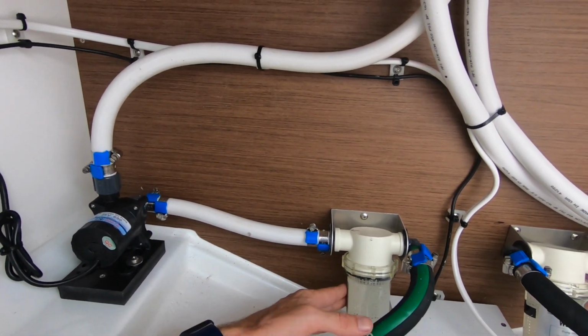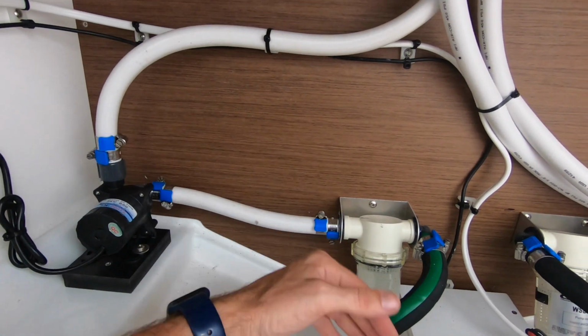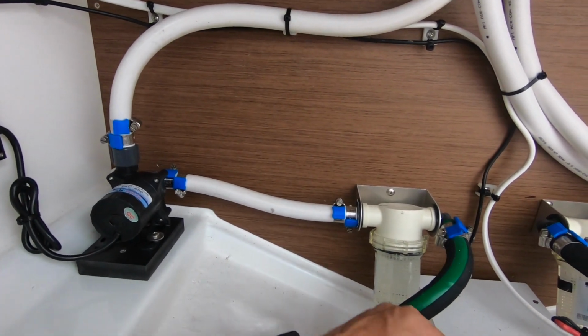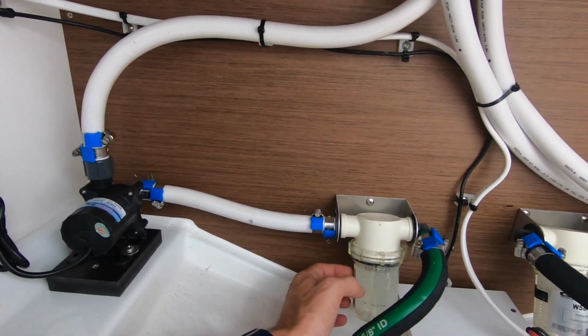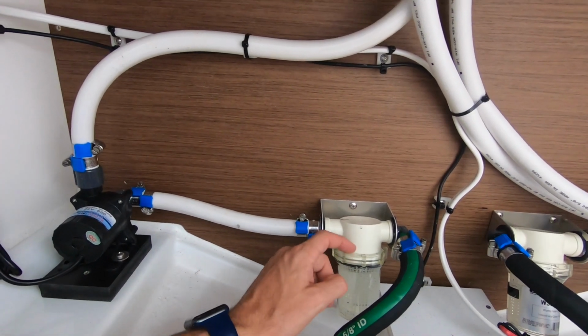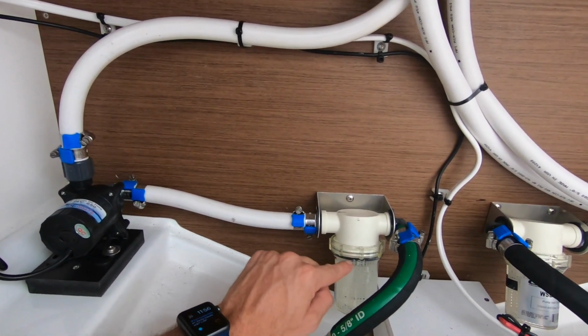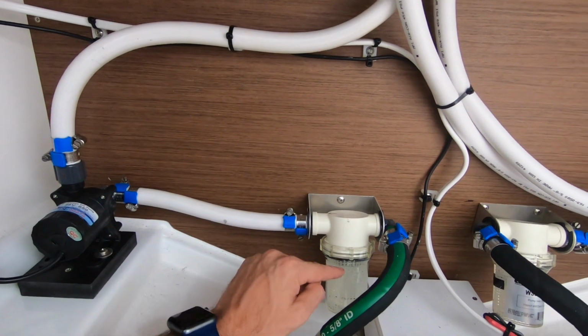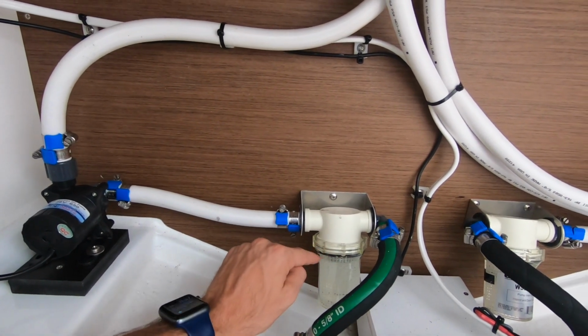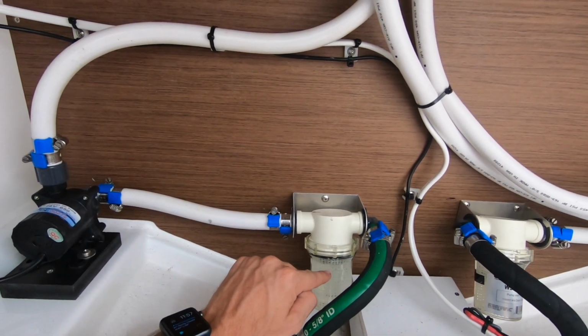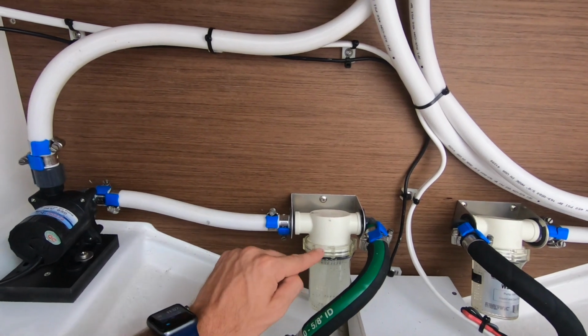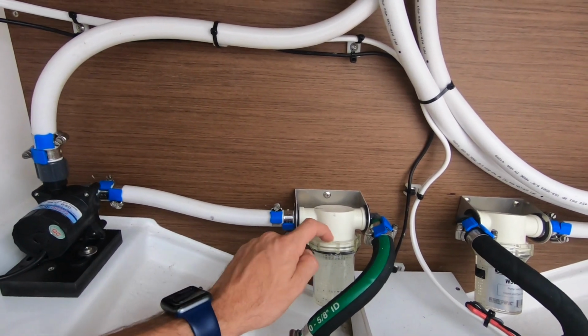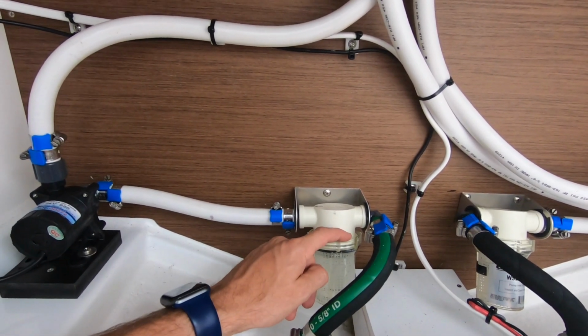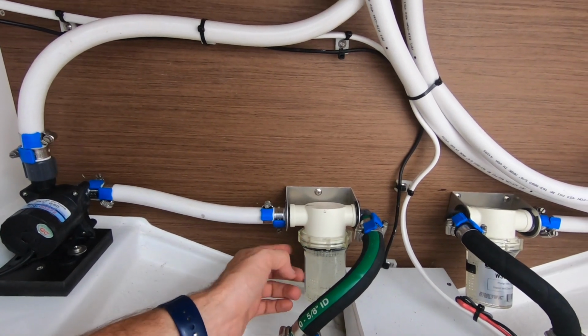If it is obstructed, turn the unit off and close the corresponding valve, take the basket off and clean it, being very careful with the inside seal. When putting it back on, make sure the seal is bedded properly and the basket is in its proper location. It has an inner part to fit into on the strainer, so if you force it in, you'll damage the basket itself.